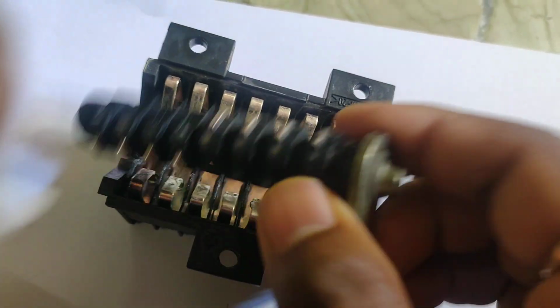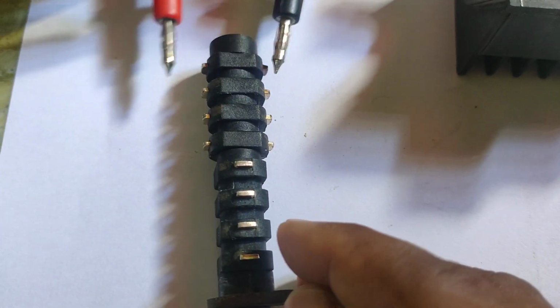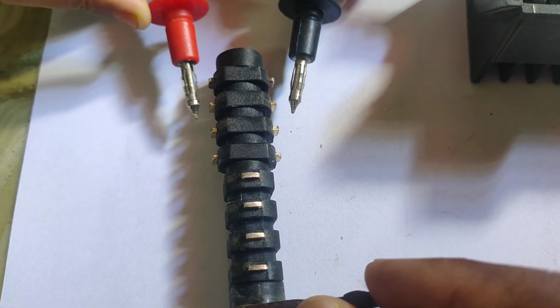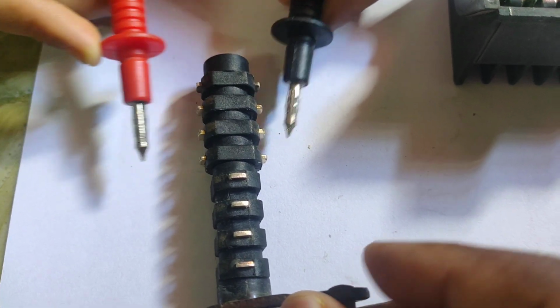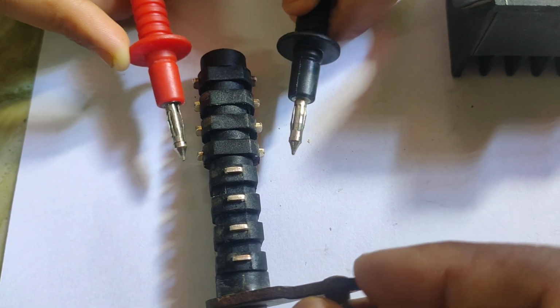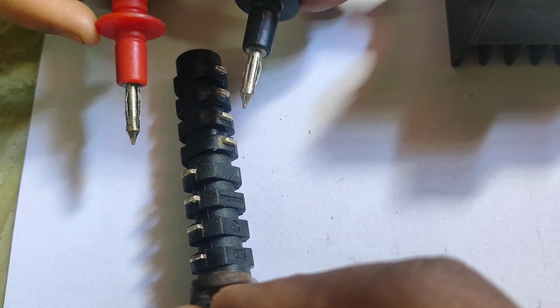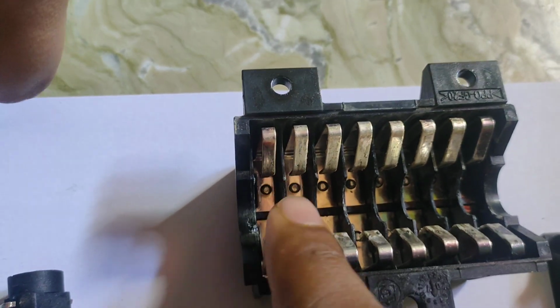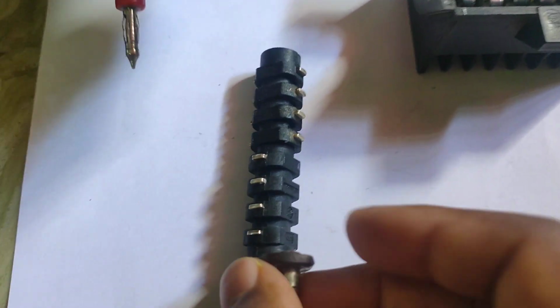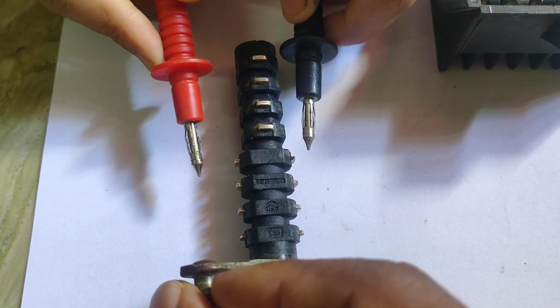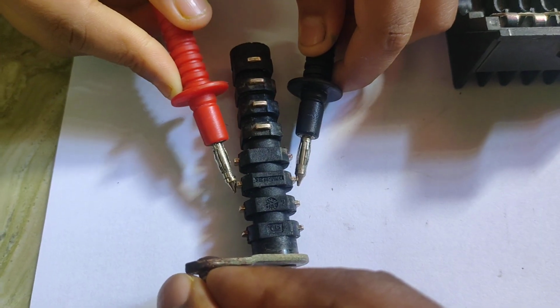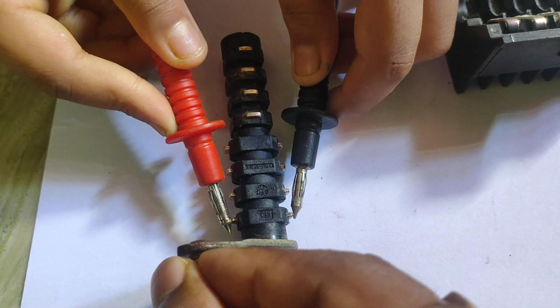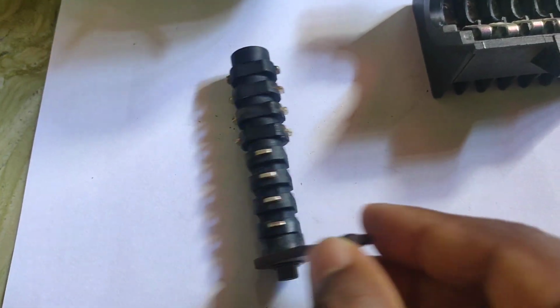I am checking that this is the NC or NO contact. I am showing you this inside switch, this latch. First contact, second contact, third contact, fourth contact. If I change these null positions, you will not get any contact, because in this path that will not be continued. Now I am just, this is the null position, I am changing these positions. So contact, next contact, next contact, next contact. By help of this mechanical latch, we are controlling the NO-NC contact.